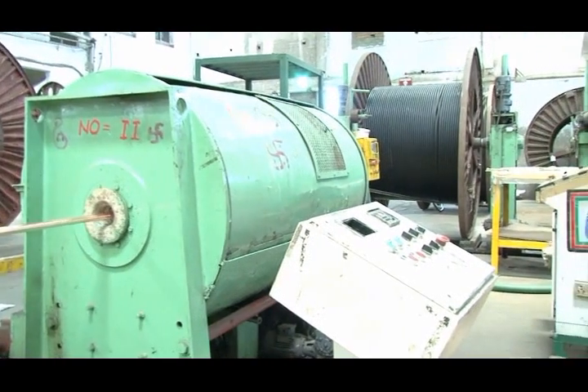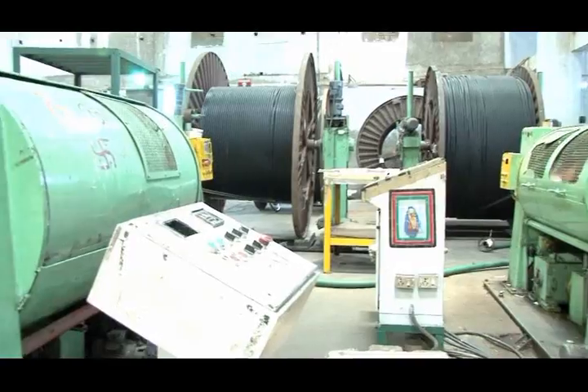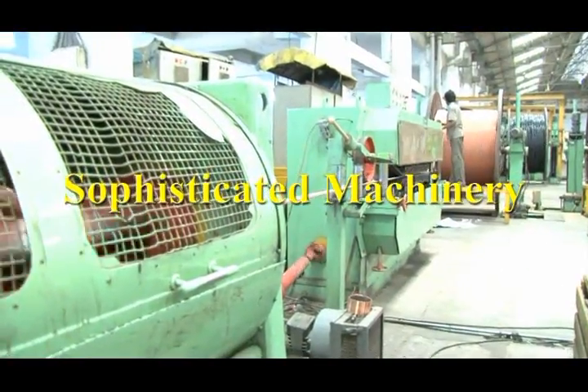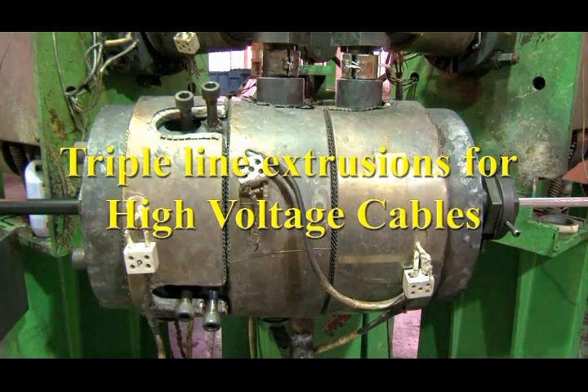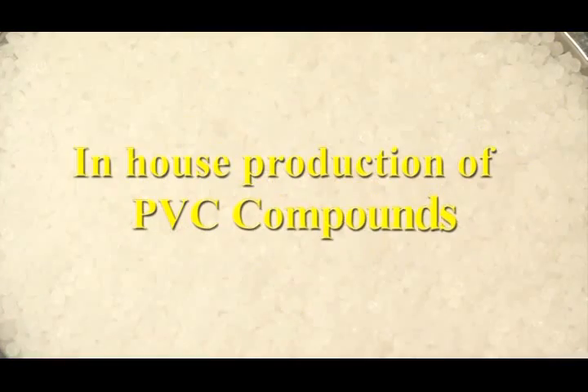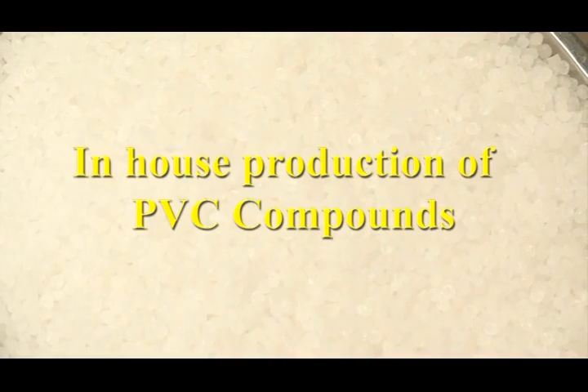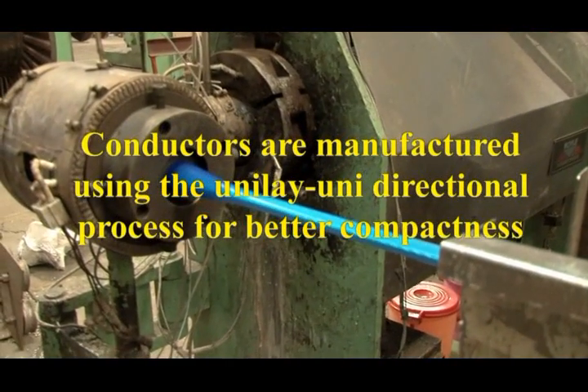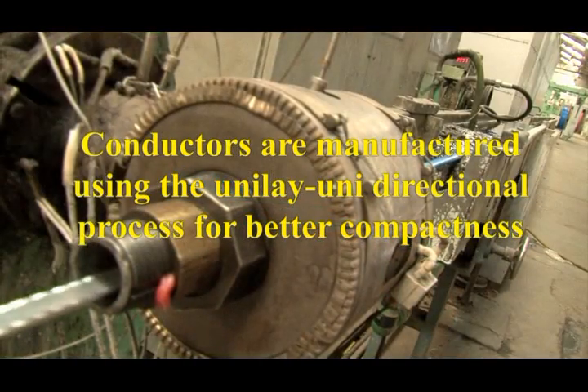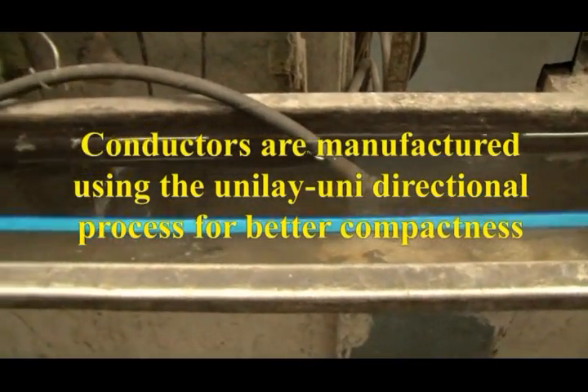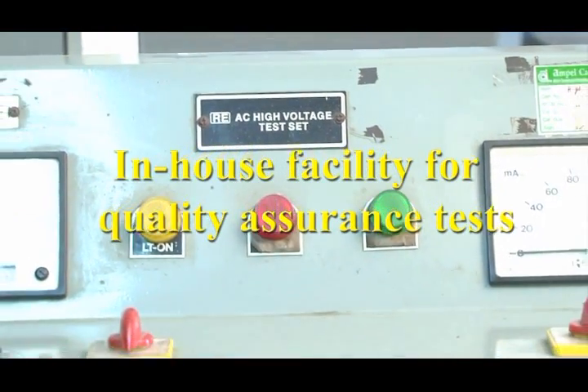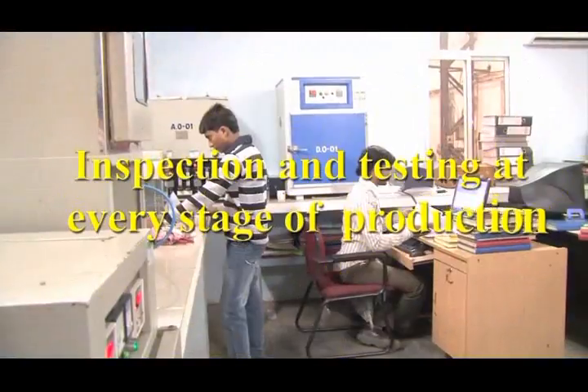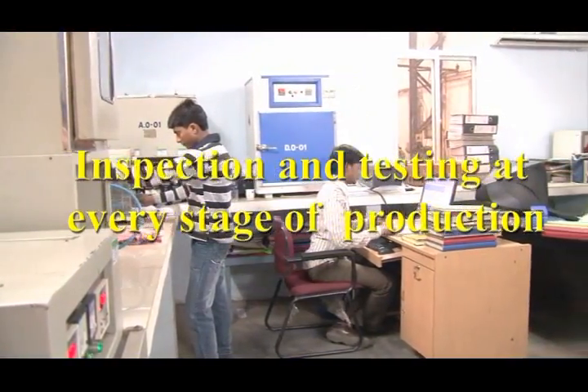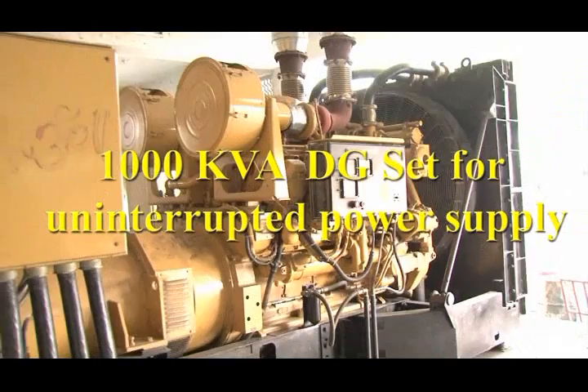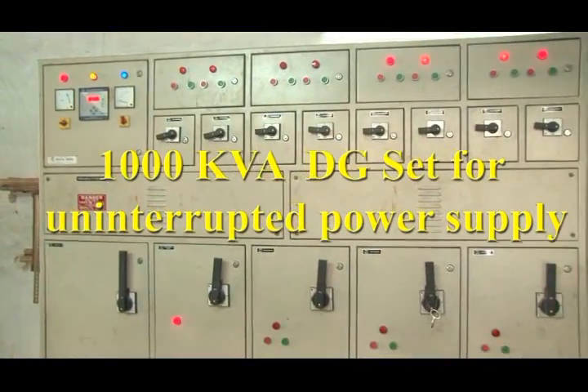This is not just a rhetoric. These words are fully backed by our strengths: sophisticated machinery, triple line extrusions for high voltage cables, in-house production of PVC compounds. We manufacture our conductors with uni-lay unidirectional process for better compactness, in-house facility for quality assurance tests, inspection and testing at every stage of production, 1000 kVA DG set for uninterrupted power supply.